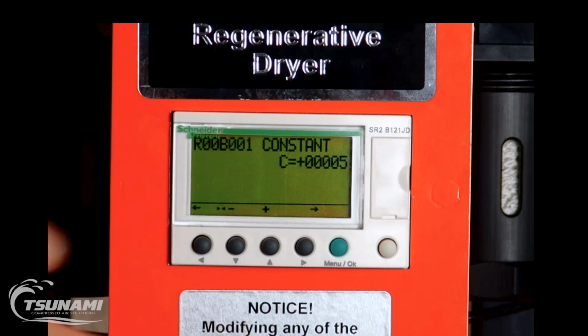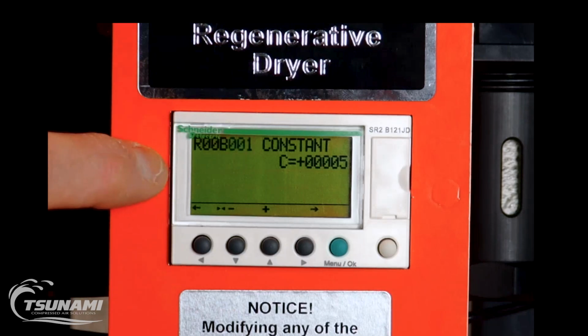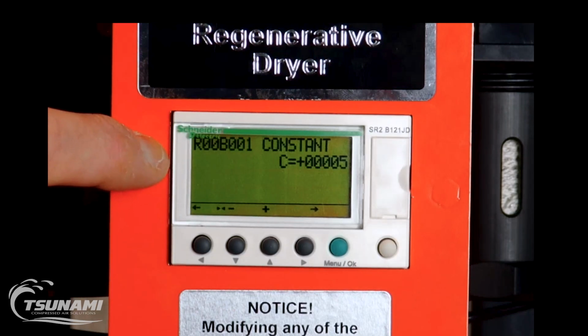On the new programs, we have 8 different inputs for block 1, which control our programming or cycle designation for the dryer. So on our 2-tower, 3-tower, 4-tower, and some of our larger rail systems, they're going to use some different programming. And the current programming also allows us to have a pause feature or just an immediate or a complete the drying cycle feature before it pauses the entire operation of drying.